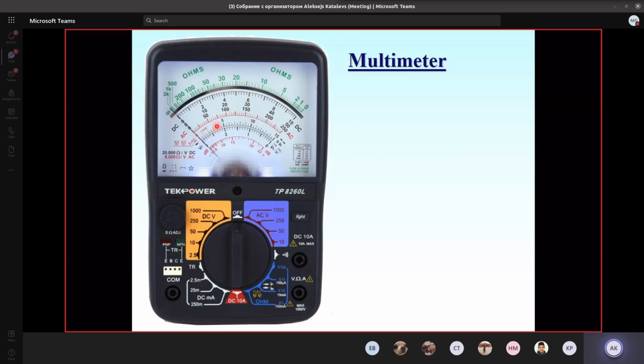From the design, it's an entirely modern device. You can see the symbol of the magnetoelectric mechanical device. You could find numbers that give the accuracy classes for AC measurement, DC measurement, and resistance measurement, along with other parameters. There are a number of scales: one for DC measurement, one for AC measurement which is a little shifted, a special scale for resistance measurement, and other types of scales.